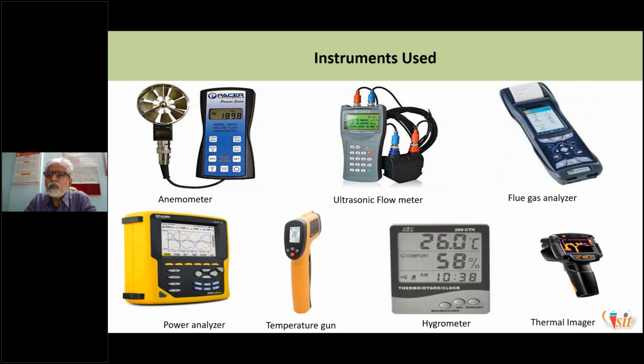And this is the flue gas analyzer, which we use to audit the furnace as well as boiler. Once we fit the probe in the chimney of the boiler or furnace, we get all the composition present in the flue gases, and on that basis we can calculate the indirect efficiency of the boiler, furnace, or wherever the combustion is being done.